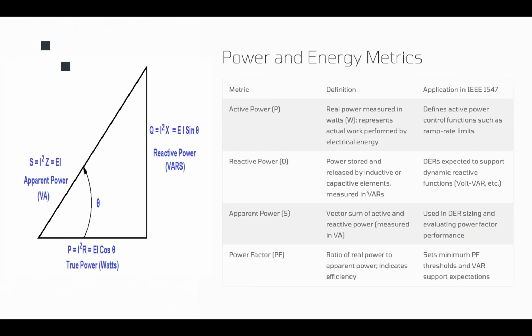Now, another metric is the reactive power. This part does not do any real work for us, but it is required to maintain the electric and magnetic fields in our system. The unit is VAR, which is short for volt-ampere reactive. Basically, it is power stored and released by the inductive or capacitive elements in our system. Now, IEEE 1547 uses this metric for voltage regulation and power quality regulation. One would be volt-VAR mode, where the DERs are asked to dynamically adjust their reactive power based on their measured local voltage, so they can help stabilize the voltage of their feeder.